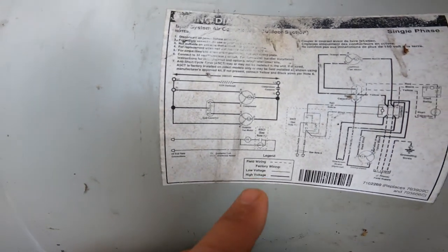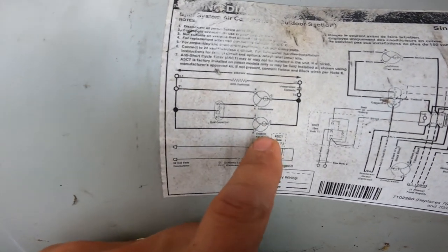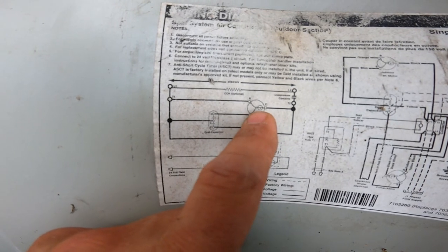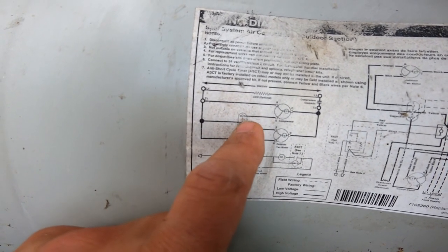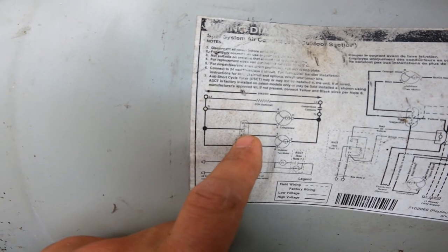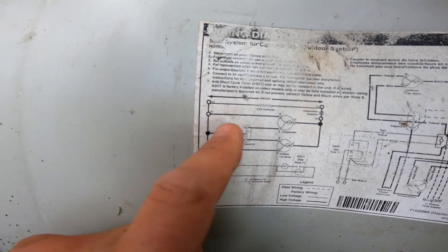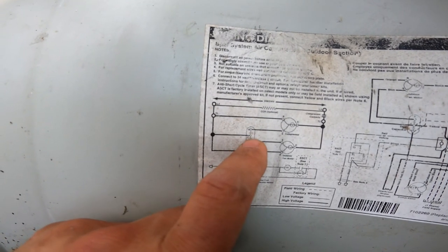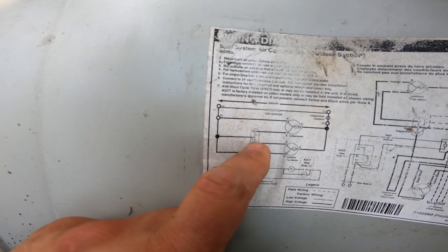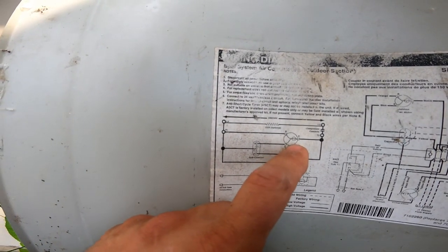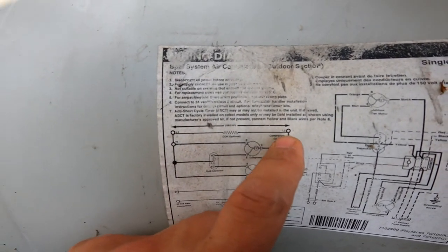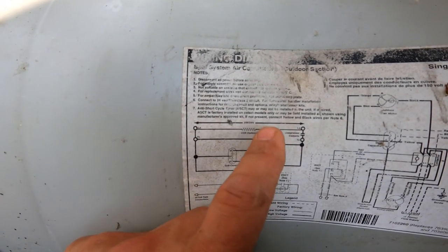Gosh, where are we? Outdoor fan motor, compressor. You know, we got fan, common, and Herm, okay? And that's a dual capacitor, okay? And there you go. Because we lost the hermetic, the compressor wasn't working, all right? So even though the compressor contacts were closing, it was not allowing it to work. So that part right there is the one that I just replaced.